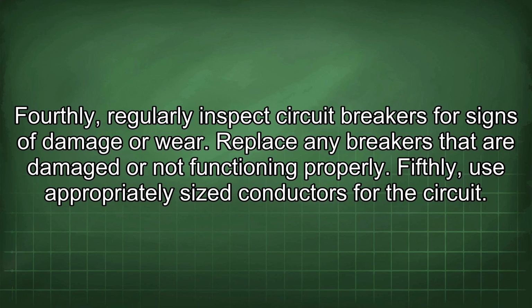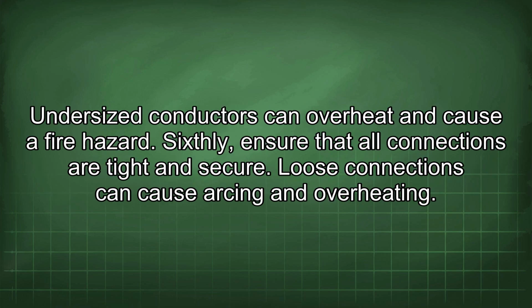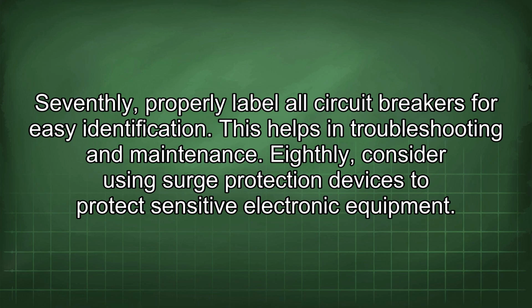Fourthly, regularly inspect circuit breakers for signs of damage or wear. Replace any breakers that are damaged or not functioning properly. Fifthly, use appropriately sized conductors for the circuit. Undersized conductors can overheat and cause a fire hazard. Sixthly, ensure that all connections are tight and secure. Loose connections can cause arcing and overheating. Seventhly, properly label all circuit breakers for easy identification. This helps in troubleshooting and maintenance.